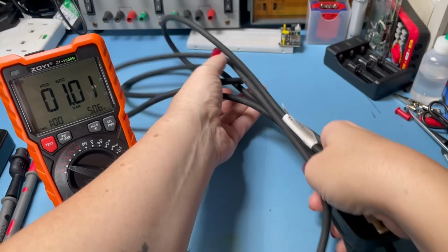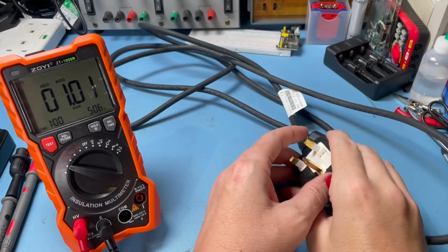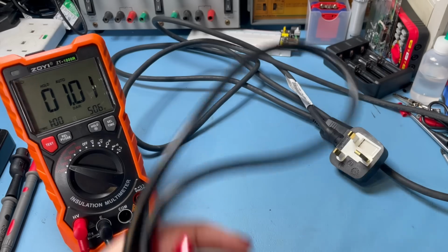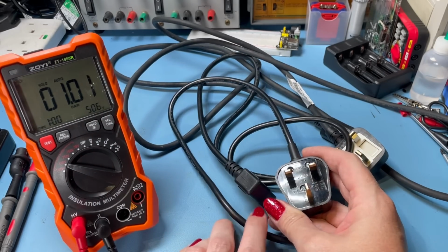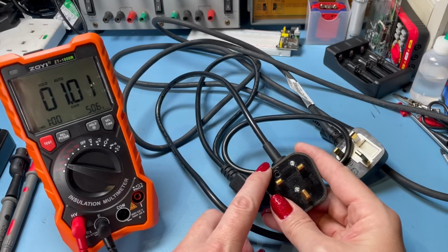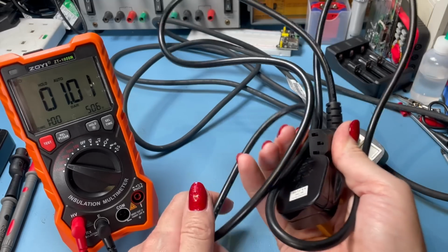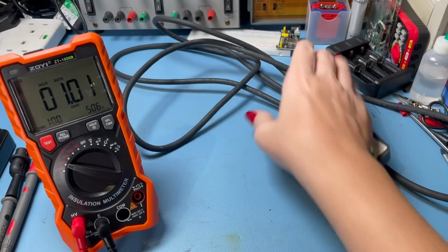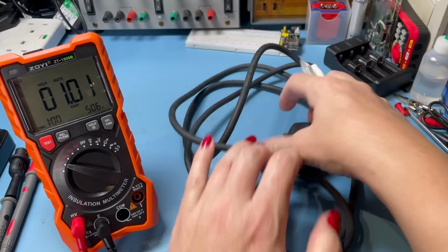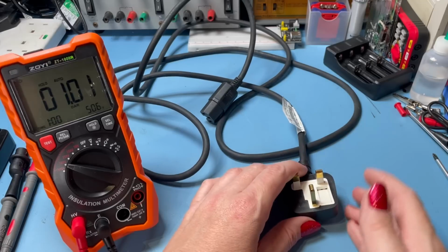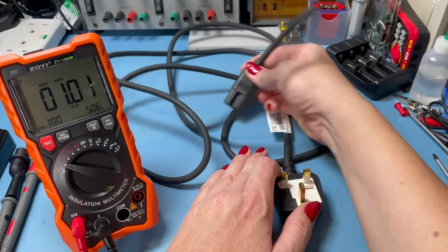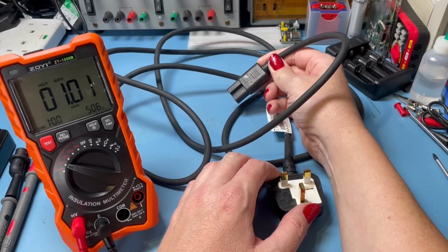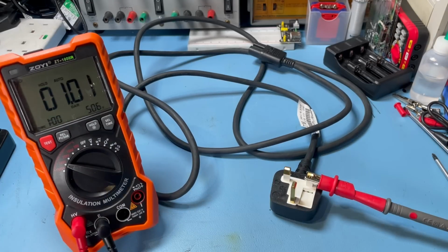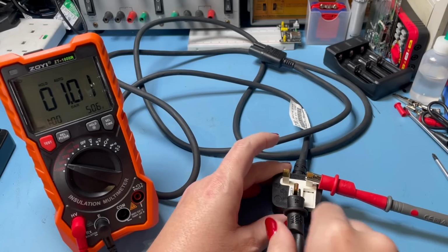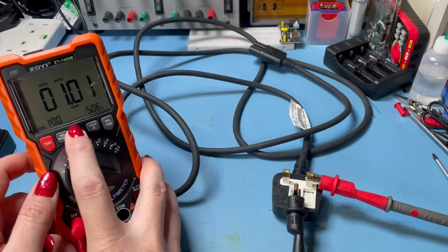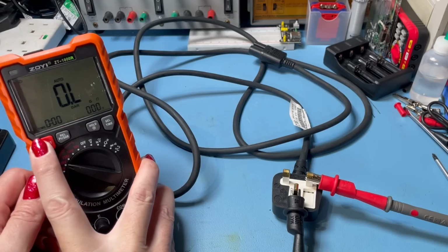So I've got two different types of kettle leads here. The first one, the insulation is rubber, and I've also got this one here which has PVC insulation. It'll be interesting to see what is the difference between these two kinds of materials in terms of insulation. So we're going to test the rubber one first. Obviously the cable length is slightly different, but these are both rated at 10 amps, 250 volts. We're going to do the same three tests that we did before: live to earth, neutral to earth, live to neutral at 500 volts. And we're going to do DAR again. Okay, let's test.